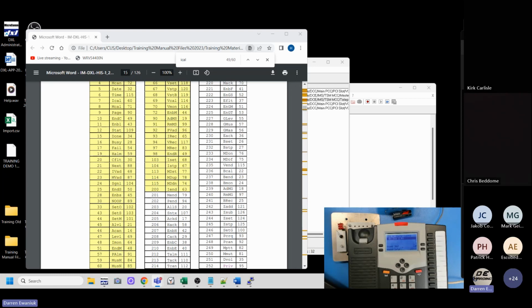A stat command, if you're using that kind of message-based response, so you send a message, you receive a message back with the 5 registers, then yes, a stat command will send you all activity. It'll send you the first one, it'll wait for you to process it, it'll send you the second one, it'll wait for you to process it, it'll send you the third one, wait for you to process it. So yes, a stat command and an all stat command will work if you're using the message-based PLC mechanism.